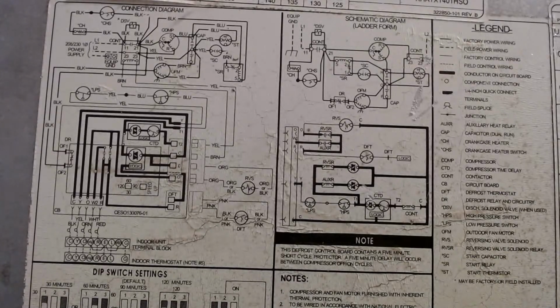So when we go through our orange wires, we go through to our RVS, which you can see the icon for reversing valve solenoid. And it just goes right back into our board. So reversing valve solenoid goes in, goes out, 24 volts. This side is your common, this side is your 24. And if we follow back down to here, we have our R and DFT, which DFT comes out and goes back into our logic board for defrost.